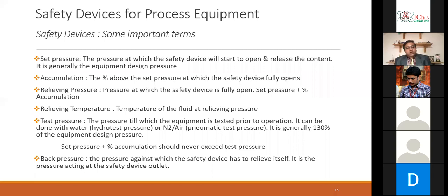One thing interesting, I don't know if you have noticed here or not, the vessel can actually see and withstand a pressure higher than its design pressure. My set pressure is generally my design pressure, which is 10 bar, for example. By the time the PSV opens fully, it is already at 11 bar, which is higher than what it is designed for. So occasionally it can see pressures higher than its design pressure, but it should never see a pressure higher than its test pressure.